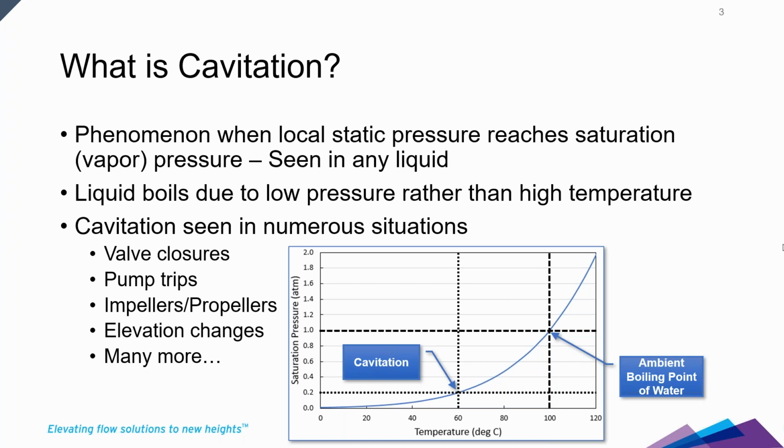And that low pressure reflection will often drop down to vapor pressure. And then on the downstream side of the valve, it very quickly will drop to vapor pressure. And so you're going to be cavitating on the downstream side of the valve significantly. So this is one of the key situations to watch out for when it comes to dealing with cavitation.